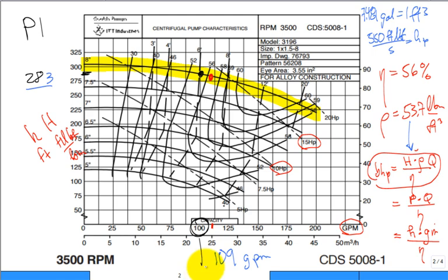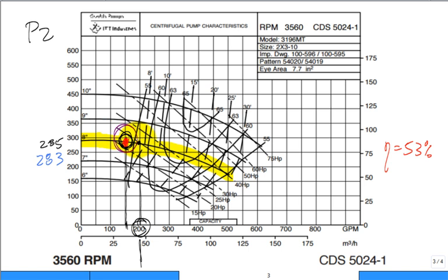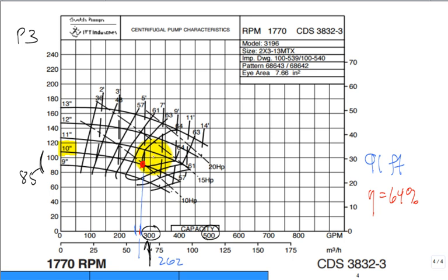I'd say, am I happy with this operating at that point? For pump 1, yeah, I can take it. That's pretty good. For pump 2, I'm a little concerned it's getting away from where it wants to be, but it'll work. It'll work. And then for pump 3, actually, that's okay, isn't it? Isn't that pretty good?